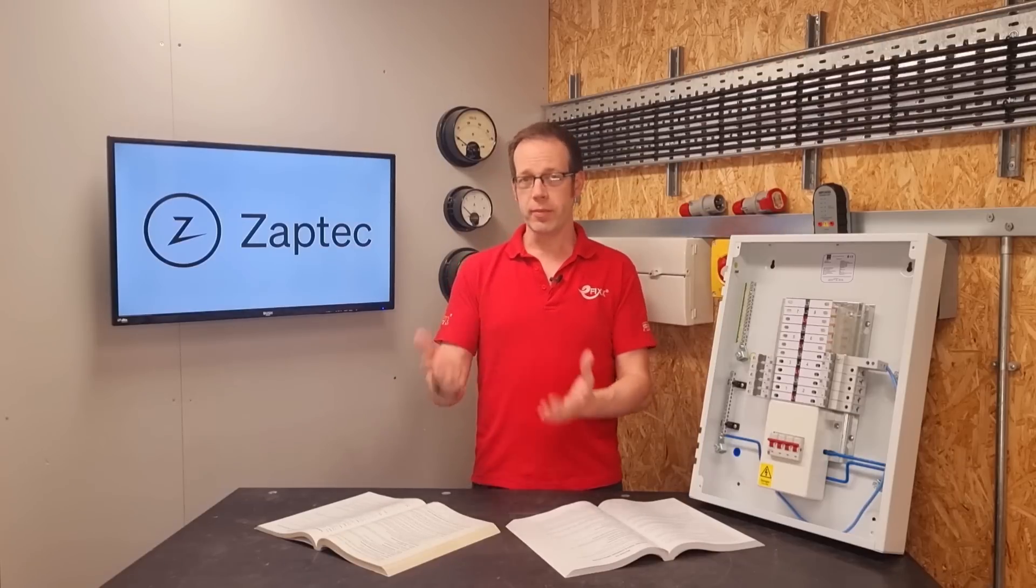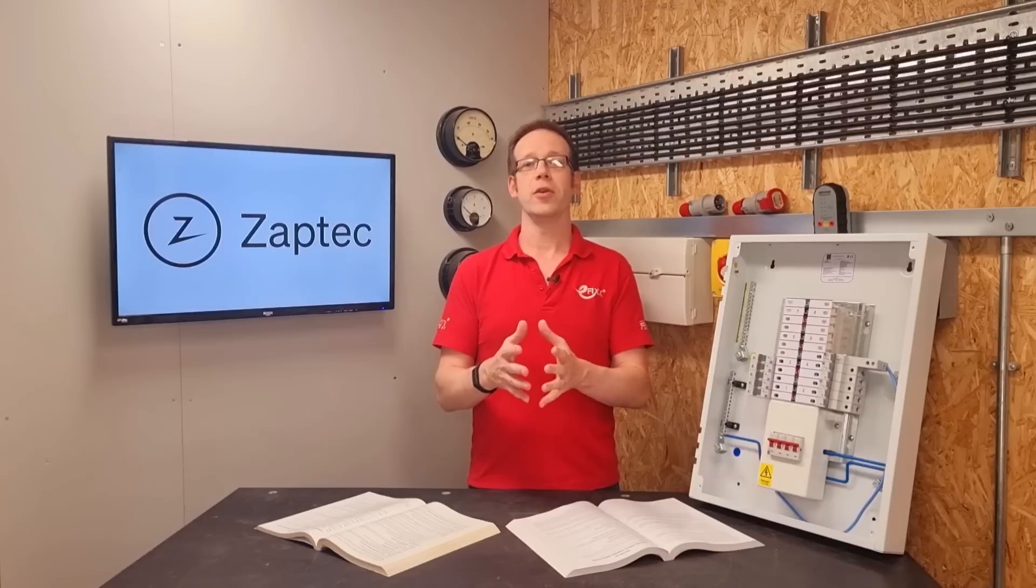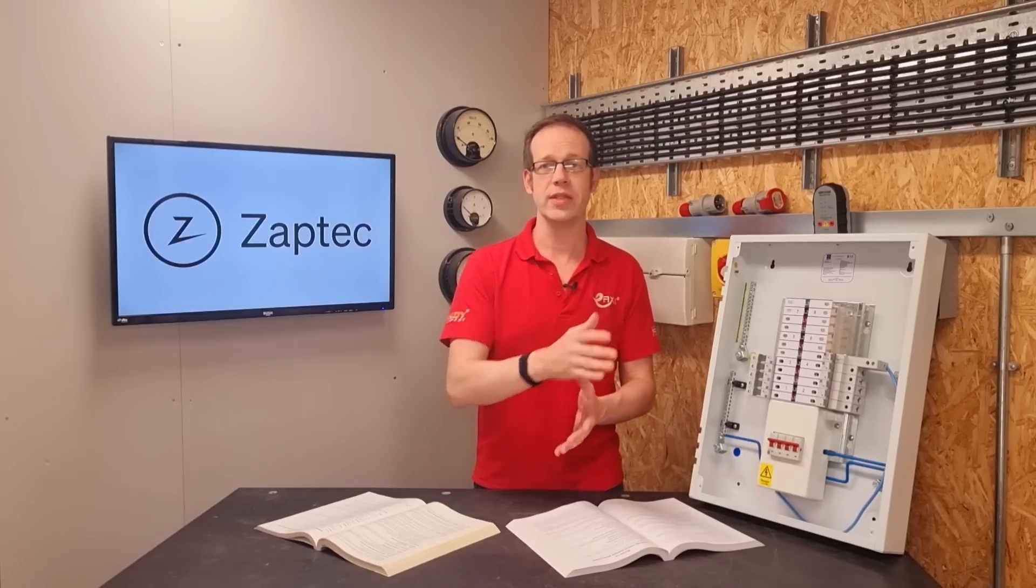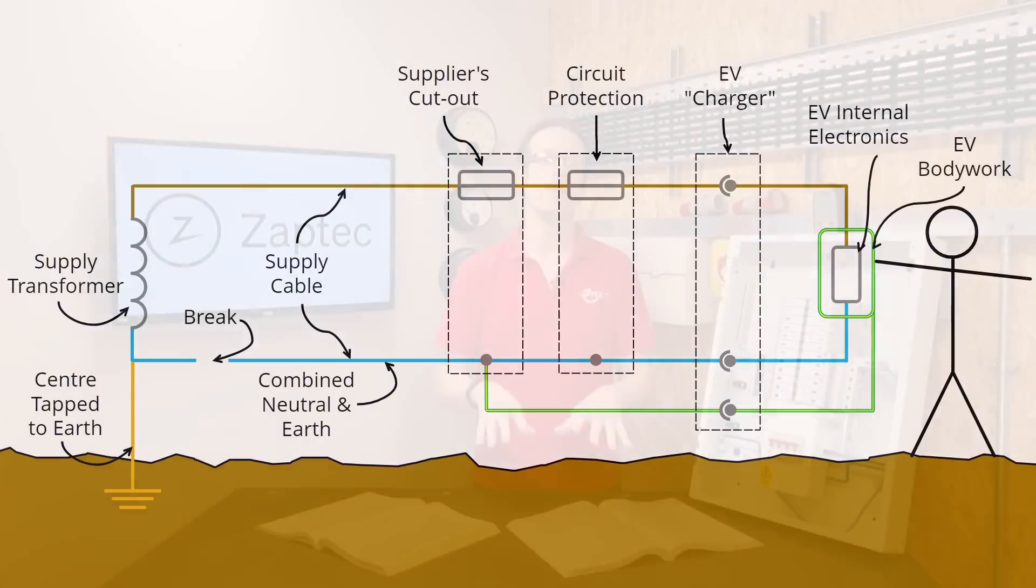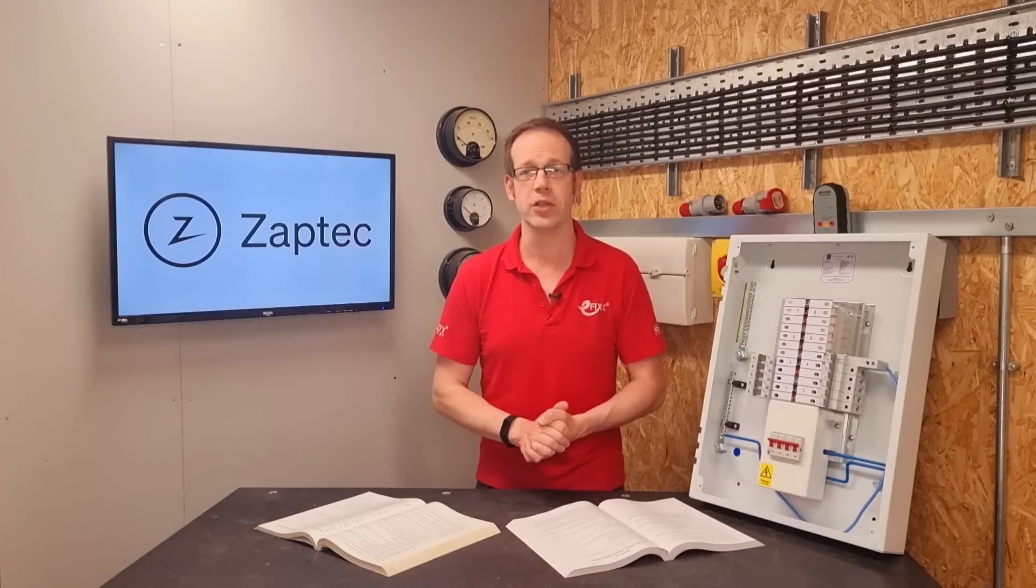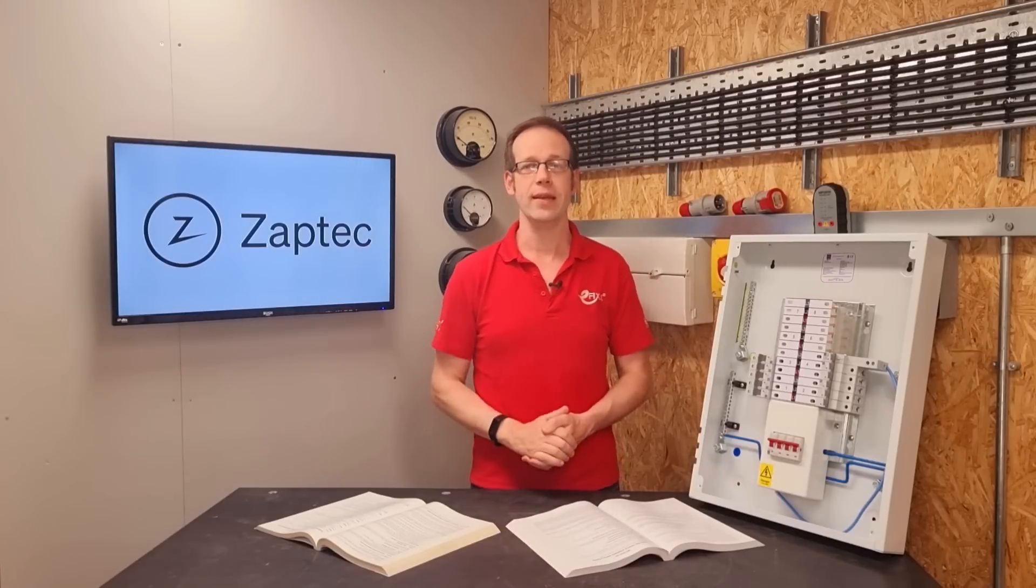Well remember the problem occurs when the combined neutral and earth conductor into the installation loses its connection and the current is looking for that route out, meaning that the voltage between the bodywork of the car and the literal earth was likely to go well above 70 volts, which is the point at which the voltage would become potentially lethal in this situation.